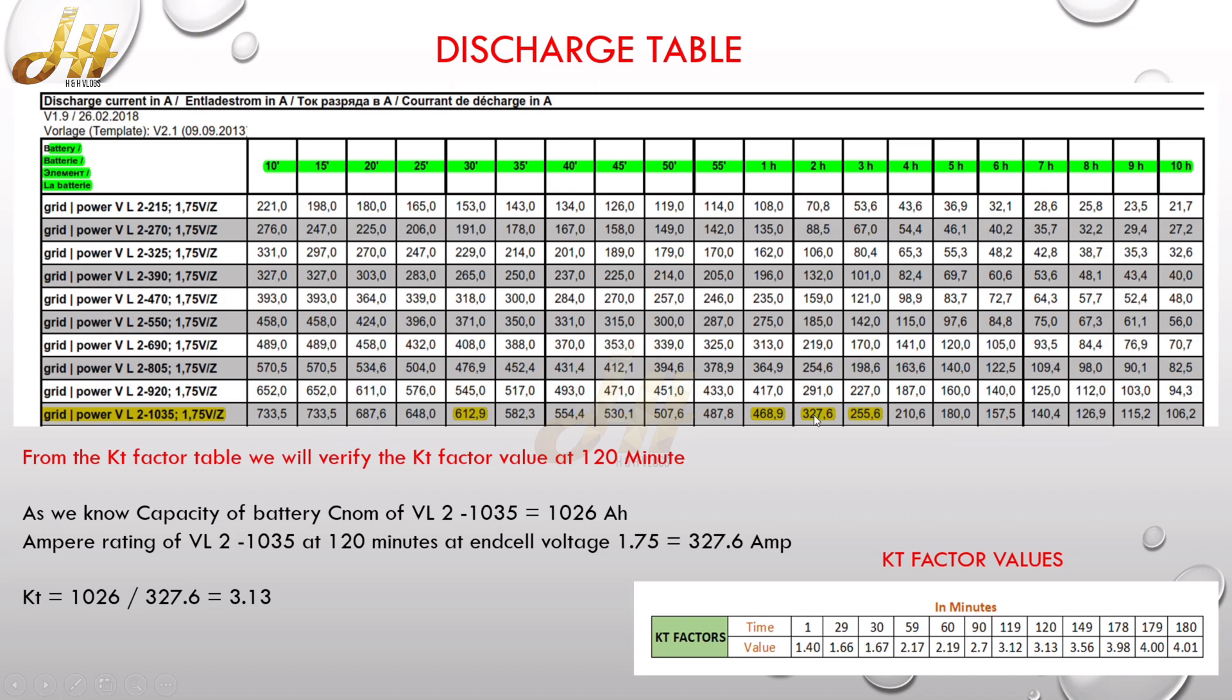So we need to divide the nominal capacity, which is 1026, by 327.6, so you can get the KT factor value as 3.13. So this is the procedure how the KT factor value can be achieved or how it can be derived.